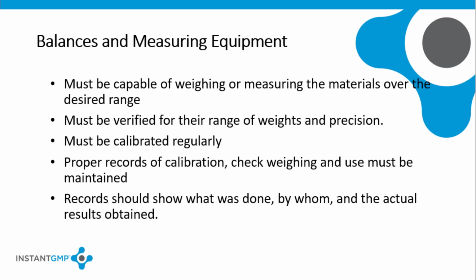Often balances and other measuring equipment are the simplest and most neglected of equipment. All balances and measuring equipment must be capable of weighing or measuring the materials over the desired range required for production and testing. Balances must be verified for their range of weights and precision. Balances and measuring equipment must be calibrated regularly. Proper records of calibration, check weighing, and use must be maintained.